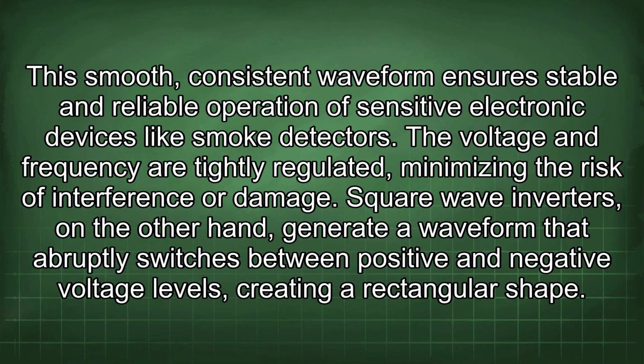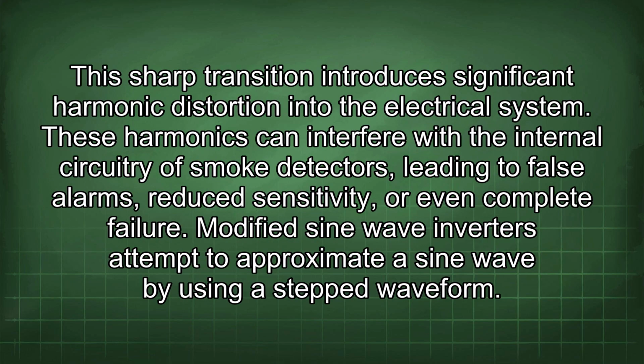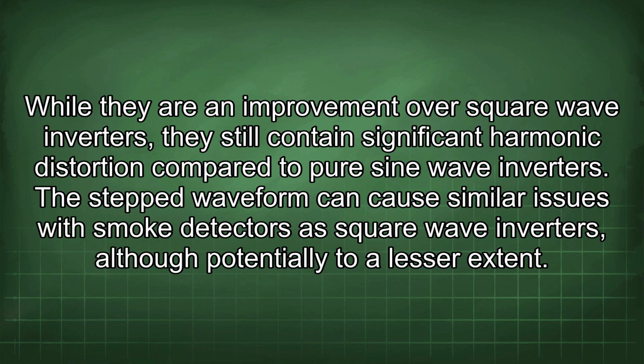Square wave inverters, on the other hand, generate a waveform that abruptly switches between positive and negative voltage levels, creating a rectangular shape. This sharp transition introduces significant harmonic distortion into the electrical system. These harmonics can interfere with the internal circuitry of smoke detectors, leading to false alarms, reduced sensitivity, or even complete failure. Modified sine wave inverters attempt to approximate a sine wave by using a stepped waveform. While they are an improvement over square wave inverters, they still contain significant harmonic distortion compared to pure sine wave inverters. The stepped waveform can cause similar issues with smoke detectors as square wave inverters, although potentially to a lesser extent.